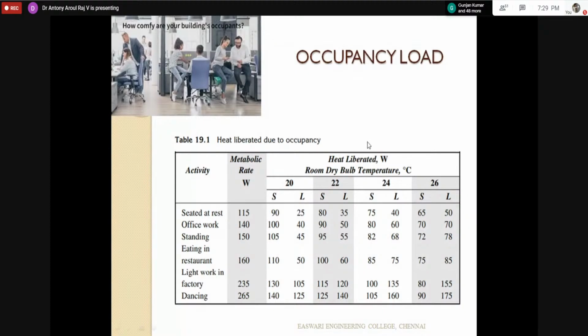If they are seated at rest, the load added is smaller. If they are active, dancing, or doing heavy work, the metabolic rate is higher, so the heat added is higher. It also depends on the dry bulb temperature. At 20°C, sensible heat is 140 and latent heat is 125. At 26°C, sensible heat is 90 and latent heat is 175.